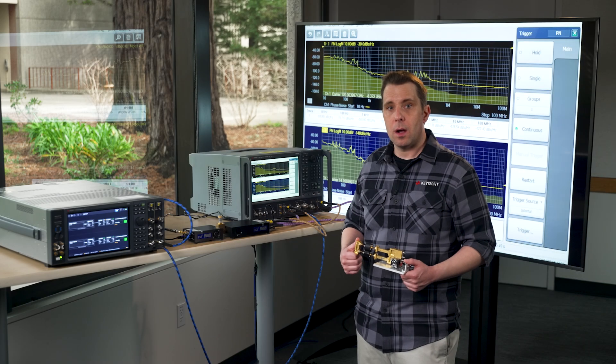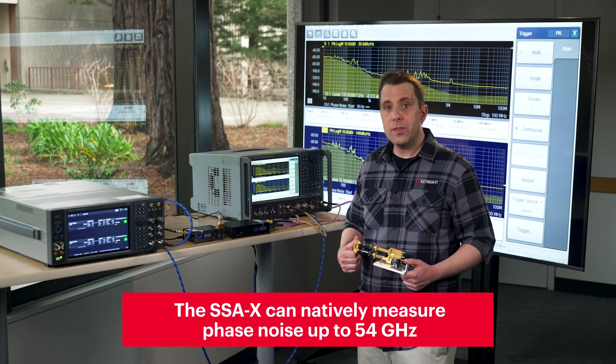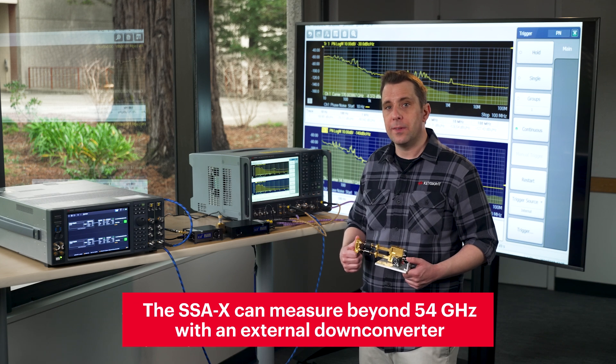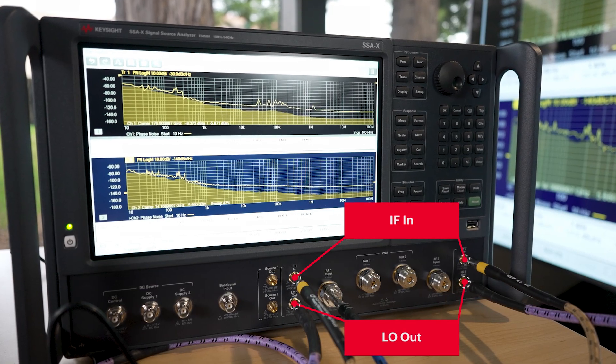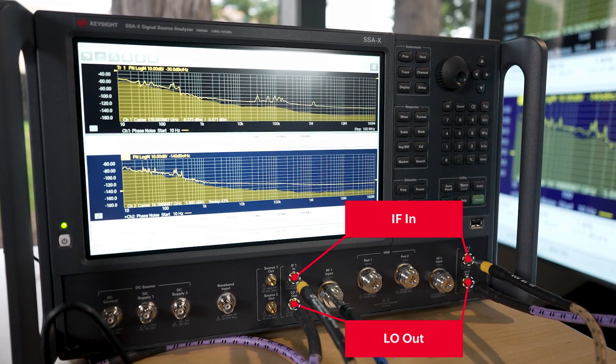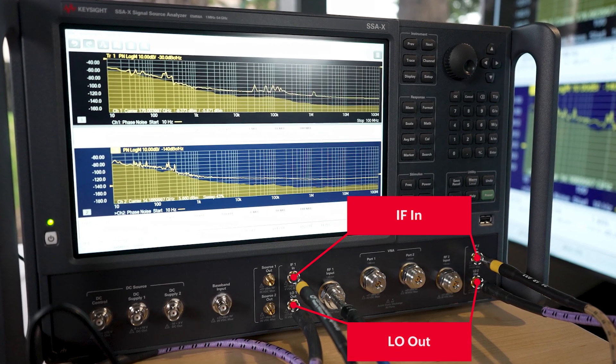As we just saw, the SSA-X can natively measure phase noise up to 54 gigahertz. It can also measure absolute phase noise beyond 54 gigahertz with an external down converter. The SSA-X has two independent LO outputs and IF inputs to enable both internal channels to be used with a dual channel down converter for cross correlation and thus higher sensitivity.